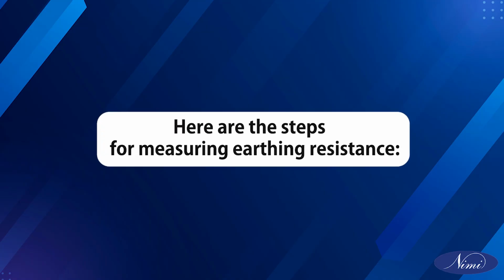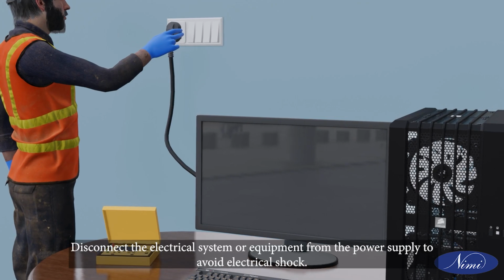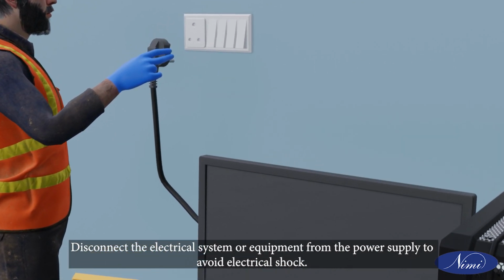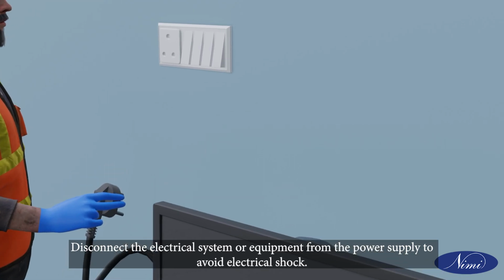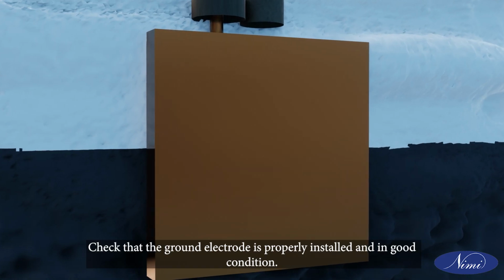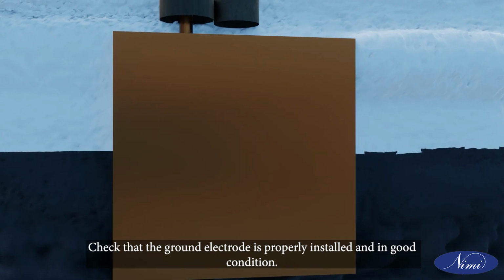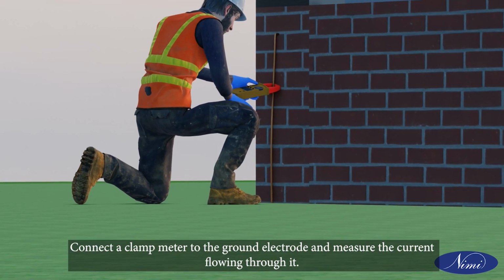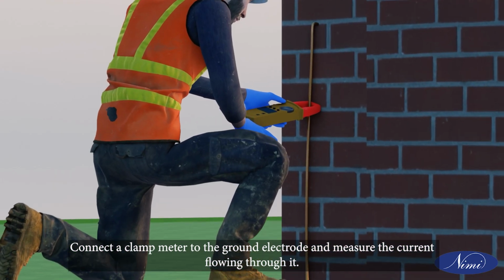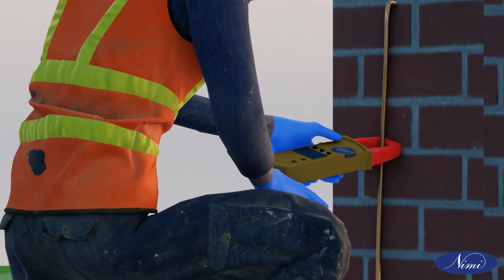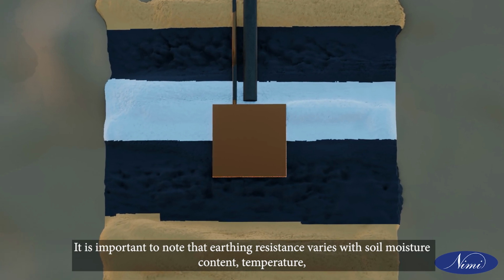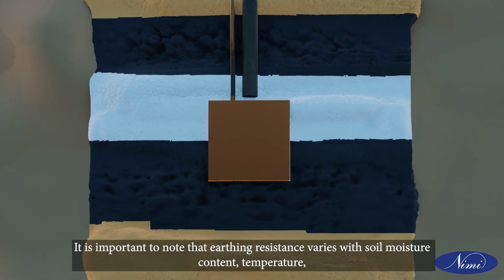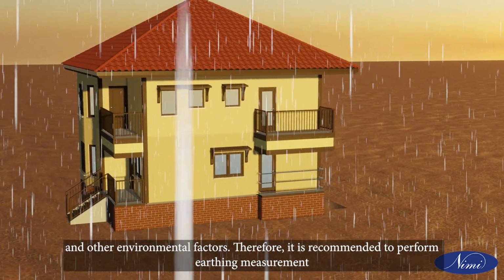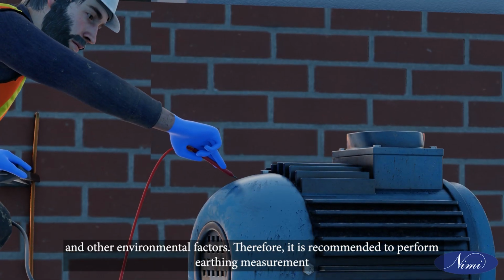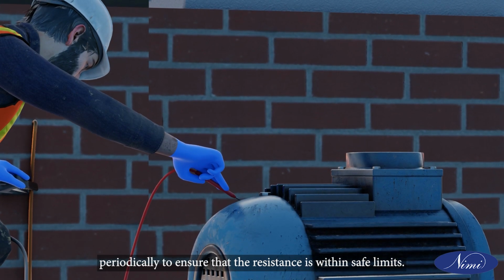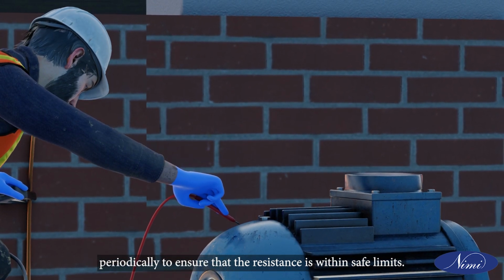Here are the steps for measuring earthing resistance. Disconnect the electrical system or equipment from the power supply to avoid electrical shock. Check that the ground electrode is properly installed and in good condition. Connect a clamp meter to the ground electrode and measure the current flowing through it. It is important to note that earthing resistance varies with soil moisture content, temperature, and other environmental factors. Therefore, it is recommended to perform earthing measurement periodically to ensure that the resistance is within safe limits.